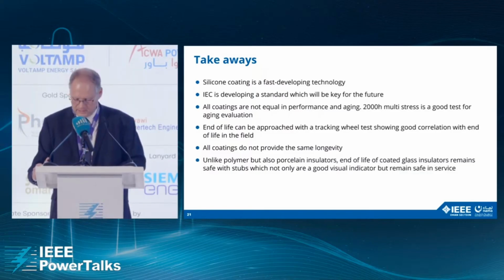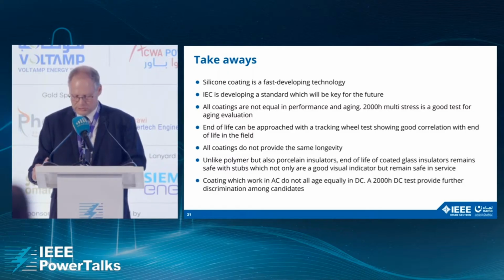Unlike polymer, but also porcelain insulators, end of life of coated glass insulator remains safe, with stubs which not only are a good visual indicator, but remain safe in service. Coatings which work in AC do not all age equally in DC. The 2,000-hour DC test provides further discrimination among candidates.